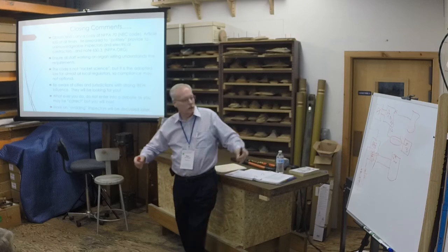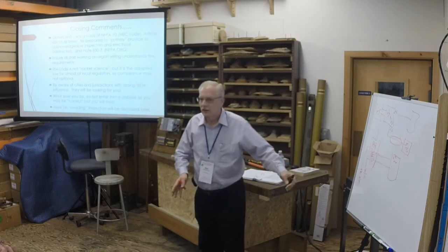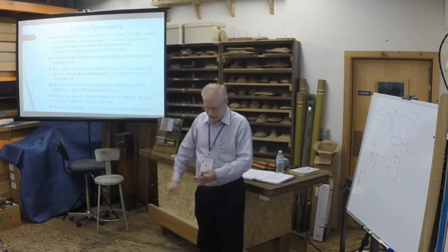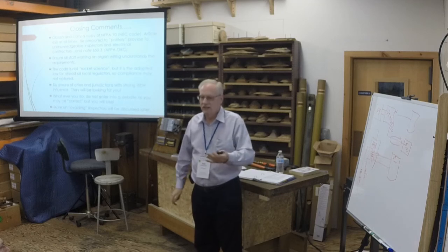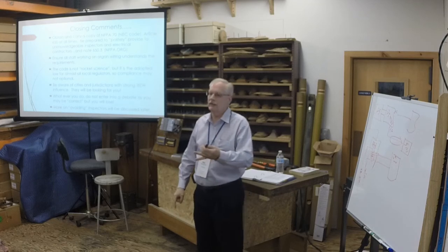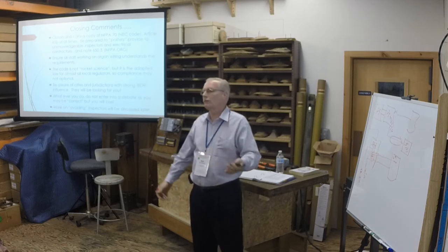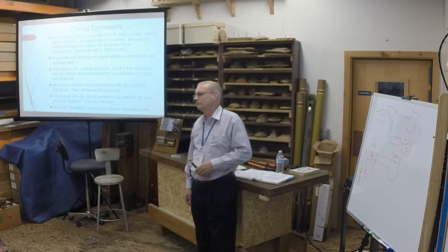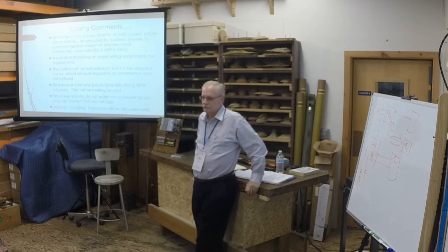If it's a short run from here to there, and you know it's never been wet, and it can't possibly be walked on, and you're not touching any single lead of it, then I might say okay. But anything more than that, if it's out of sight, if it's in the ground in a piece of conduit or something, I'd say plan B, man.